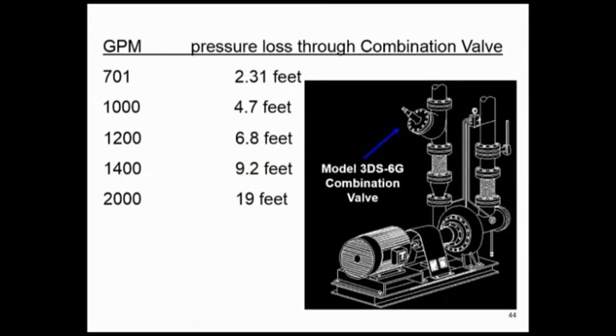That formula was, if I know the flow rate, I know the pressure drop. If I got those two numbers, I can give you the flow rate and/or pressure drop at any other setting you want. And that's all I've done here. I constructed the characteristics, CV-wise, of this valve. By the way, the CV of this valve, in case you hadn't picked up on it, was 701.